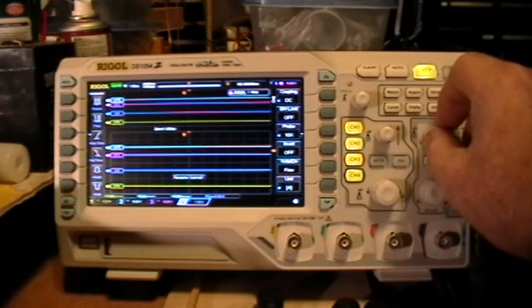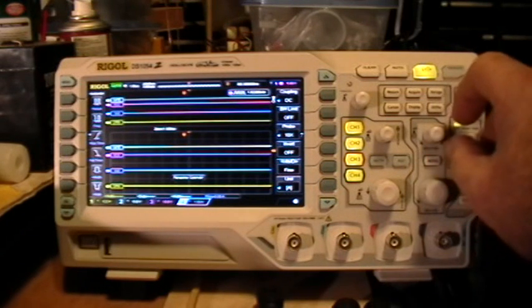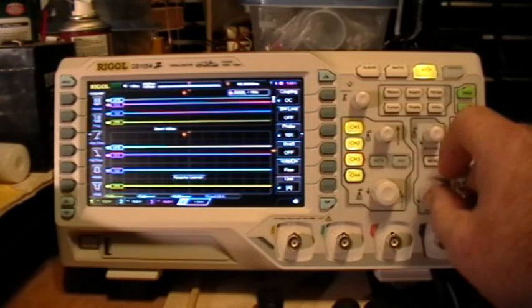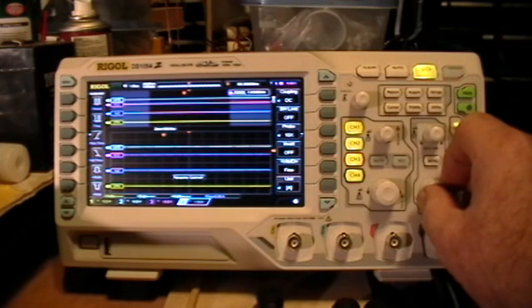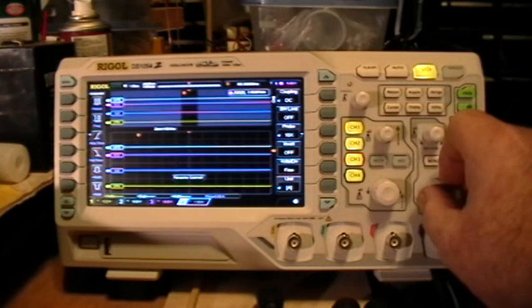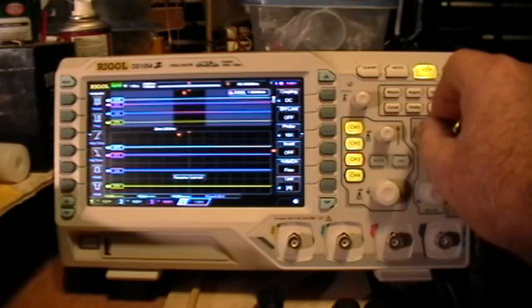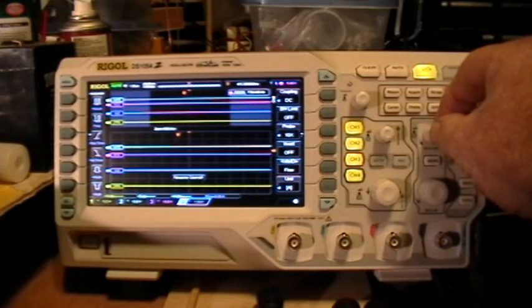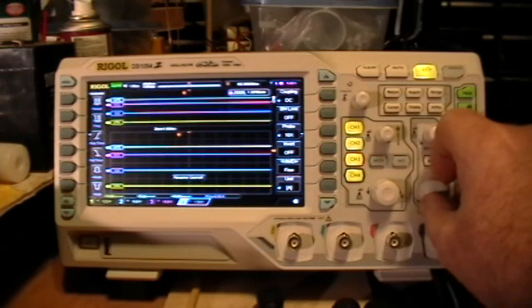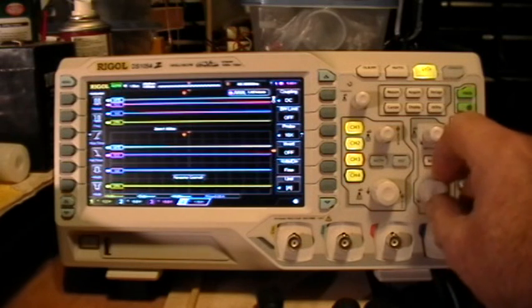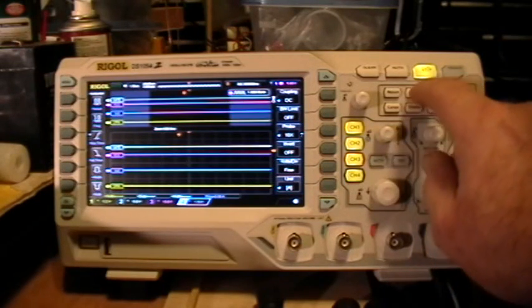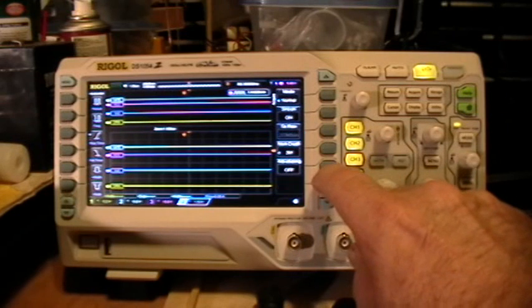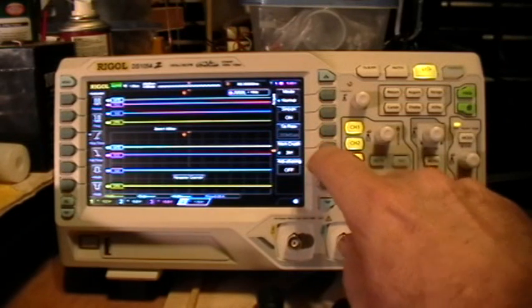We are not frozen. Because we had something other than Auto Set in the Acquire menu.